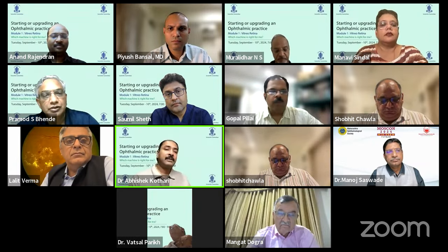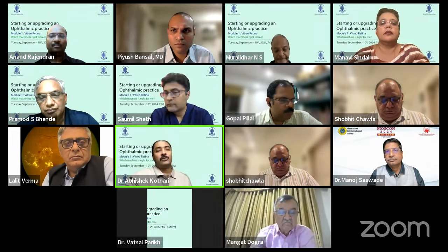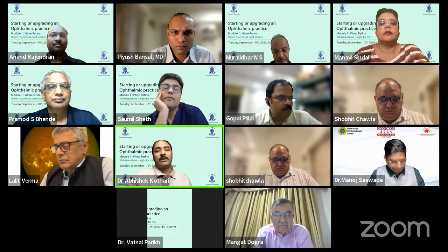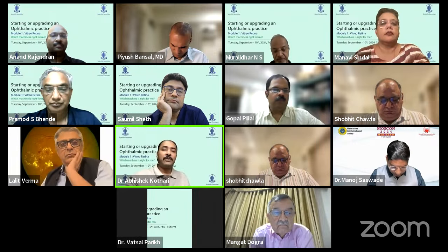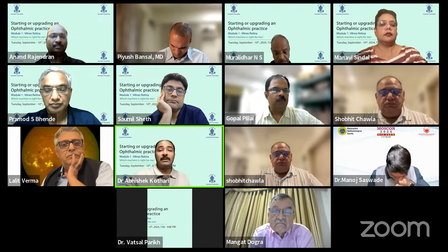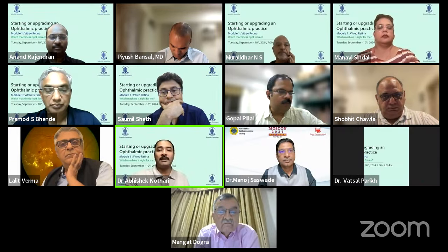Right. And the second thing that I wanted to point out was that, in some of the Indian machines, what we have seen is that the actual power delivered versus the power that you have targeted does not have a linear function. Sometimes even at lower powers, high powers get delivered. So during macular laser, this can be a bit of a complication. The accuracy of these machines is not absolutely great. So that is something you should have in mind, because this is unlike a diagnostic device. This is a therapeutic device where a mistake can cost dearly.